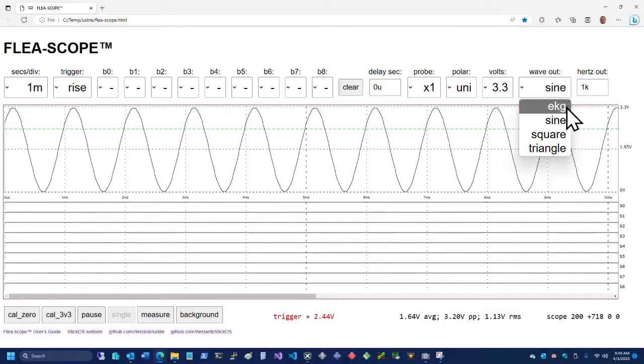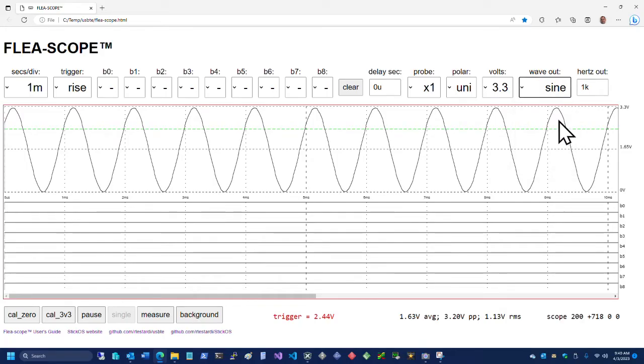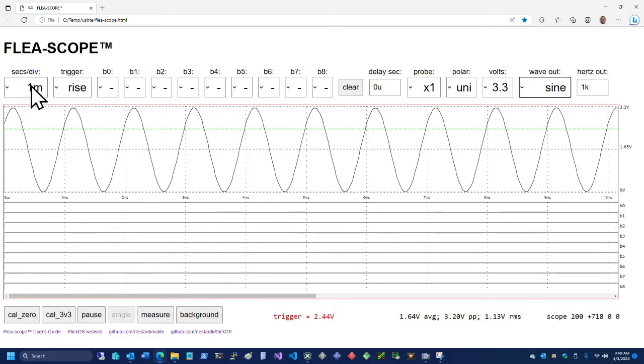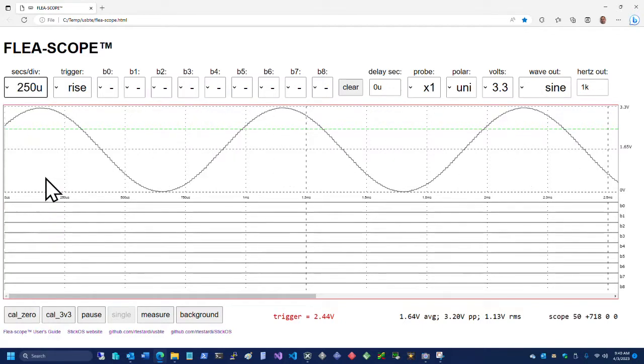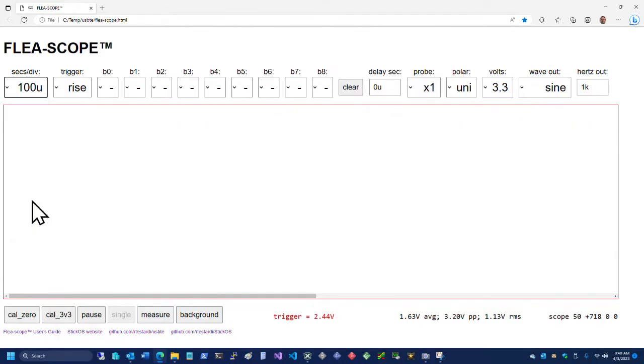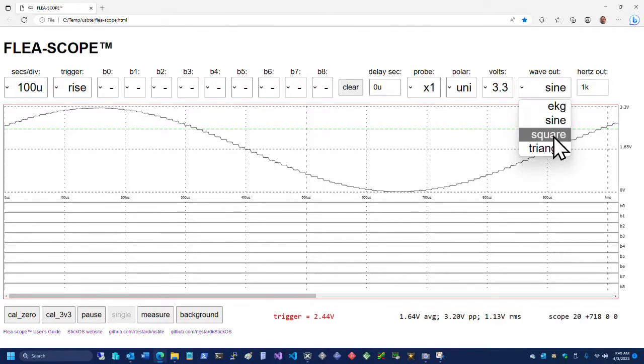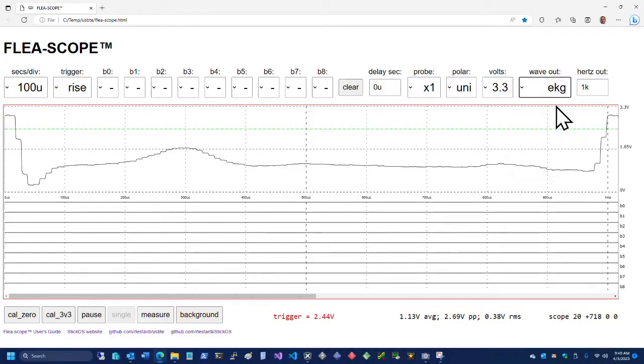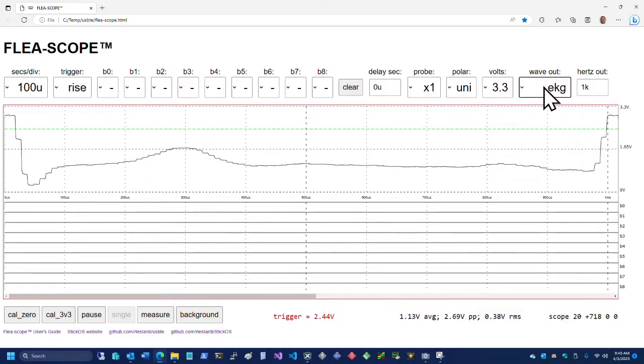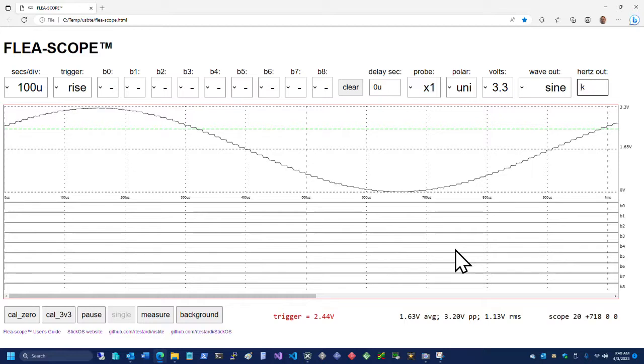We can change the frequency of this guy. These EKG sine and triangle waves are what are considered arbitrary waveform generators. They are generated through a digital to analog converter. The digital to analog converter, actually, let's show this, is generating about 100 samples per cycle. So if we were to zoom in here, you'll begin to see the artifacts of the 100 steps per cycle. And actually, if we zoom in more, you're going to see, you'll definitely see the steps here. This is what's coming out of the digital to analog converter. If we were to go into the EKG, you're going to see this again. You see the steps that's actually occurring.